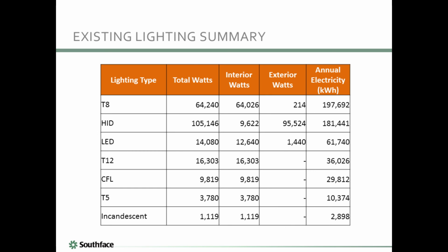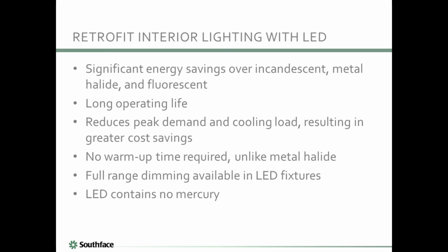LED lighting installed in the natatorium actually consumed the third most electricity. Even though it's really efficient, there was quite a lot of LED lighting. There's still T12 lighting remaining in 5 out of the 6 recreation centers. Replacing T12 lighting can produce a good payback. CFL fixtures weren't common in recreation centers. Most of the CFL fixtures were 2x2 troffers that had CFL lamps.